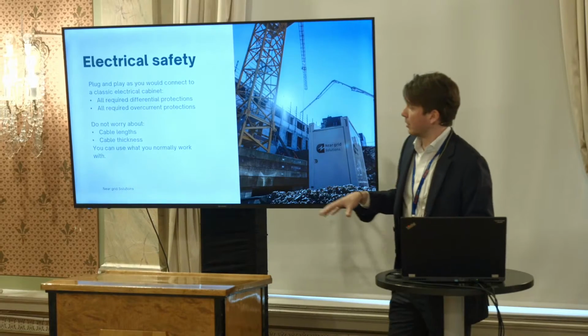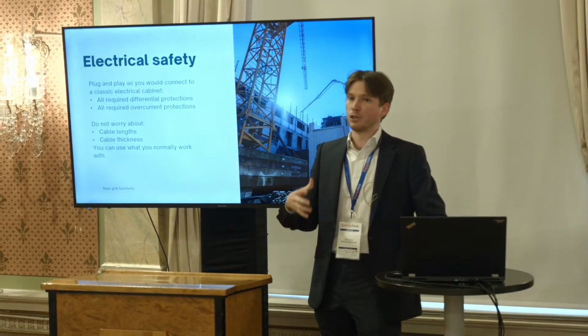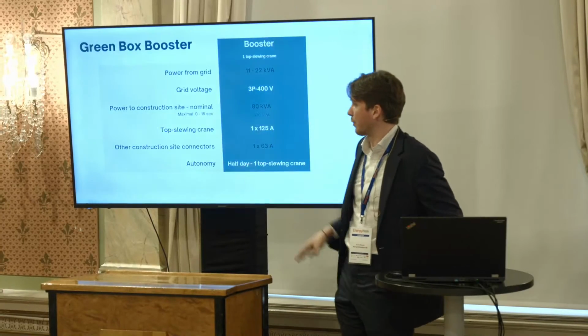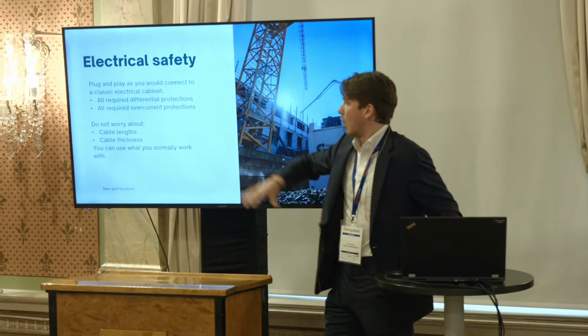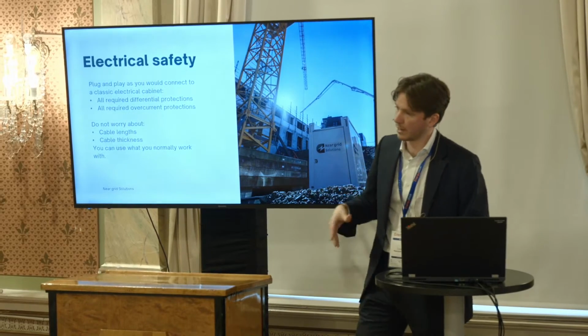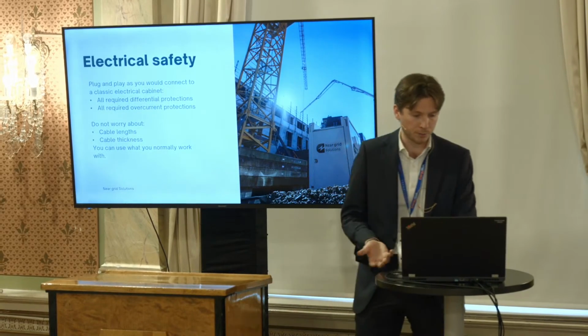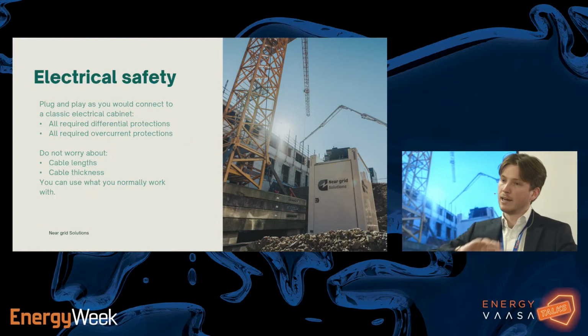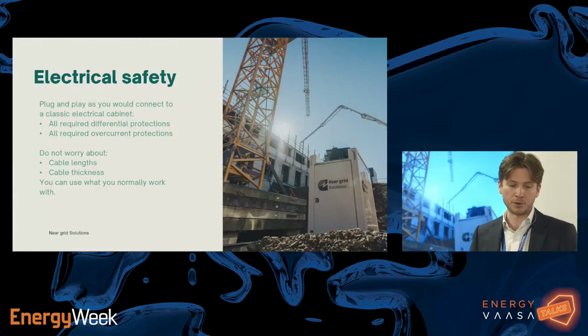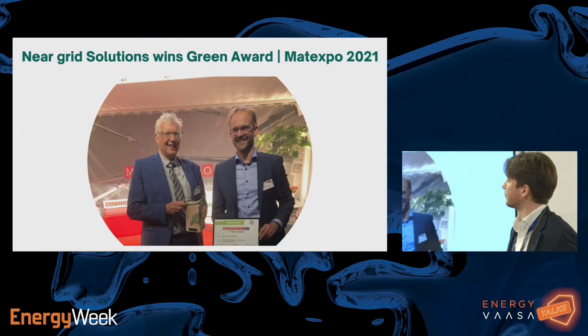We also focused in our system on a plug-and-play principle, so for the people on the construction site, there should be no difference between a diesel generator and our system. It should be very easy to install, easy to use, with little setup needed. They also don't have to worry about cable lengths and thicknesses. All the required differentials are in it, all the required overcurrent protections are in it. It's a completely engineered system with a PLC steering everything.